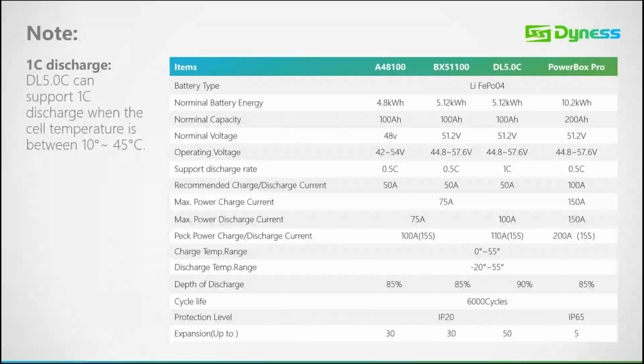The Powerbox Pro is a 10.2 kilowatt-hour battery with a 200 amp hour capacity at 51.2 volts. It supports a discharge rate of 0.5 C with a max power discharge current of 100 amps, with a depth of discharge of 85% with the IP protection of 65, and can be expanded up to 5 units in parallel. With regards to the Powerbox Pro and the IP protection, even though we do recommend it as an outdoor unit, we do recommend installers to install it under either a carport and away from direct sunlight.